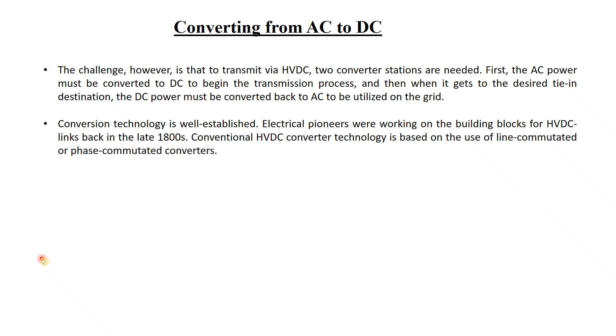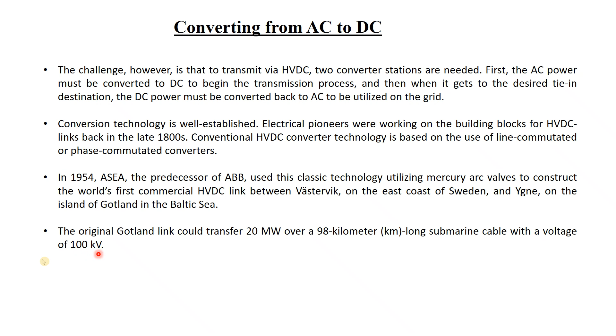The original Gotland link could transfer 20 megawatt over a 98 kilometer long submarine cable with a voltage of 100 kV. This is just information that it was first introduced: a submarine cable, under the river or under the sea, was actually used for HVDC transmission. The service was re-engineered in 1970, increasing the capacity to 30 megawatt, and the voltage to 150 kV, with the addition of a thyristor valve bridge.